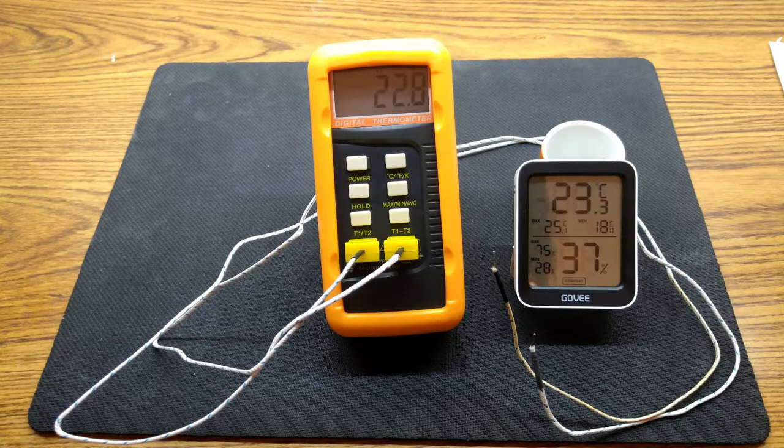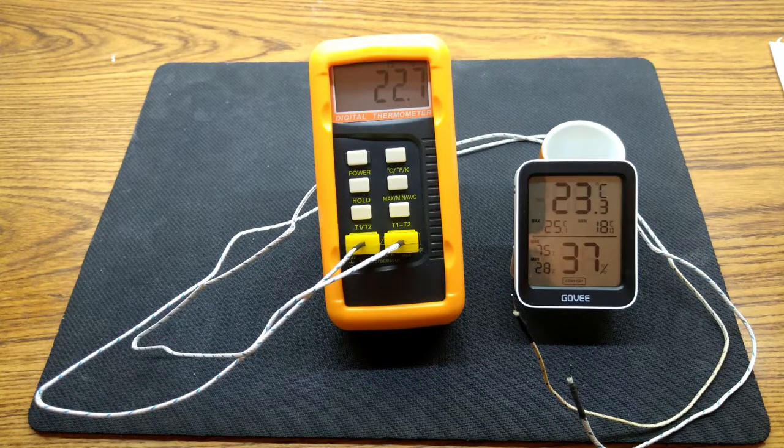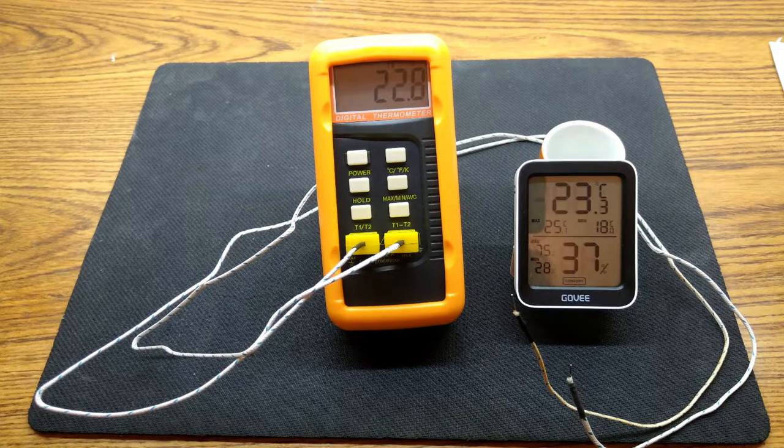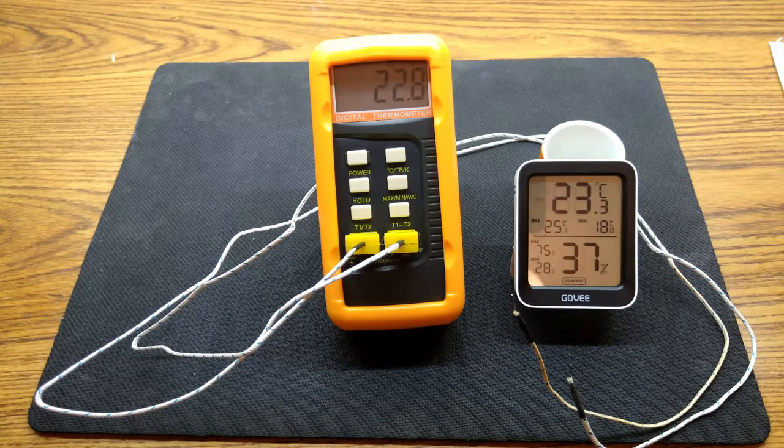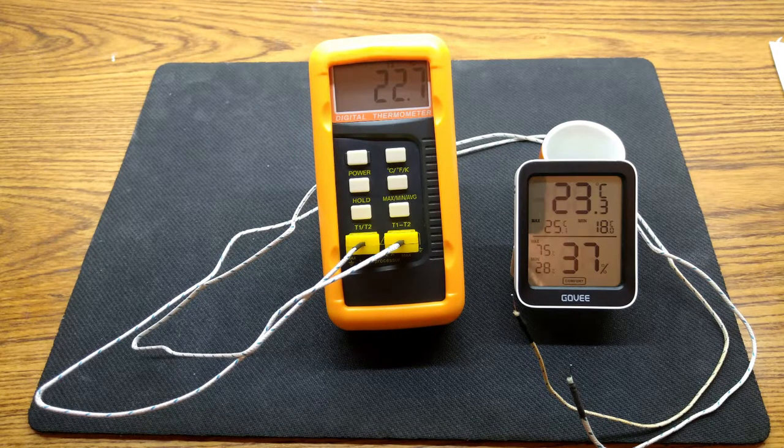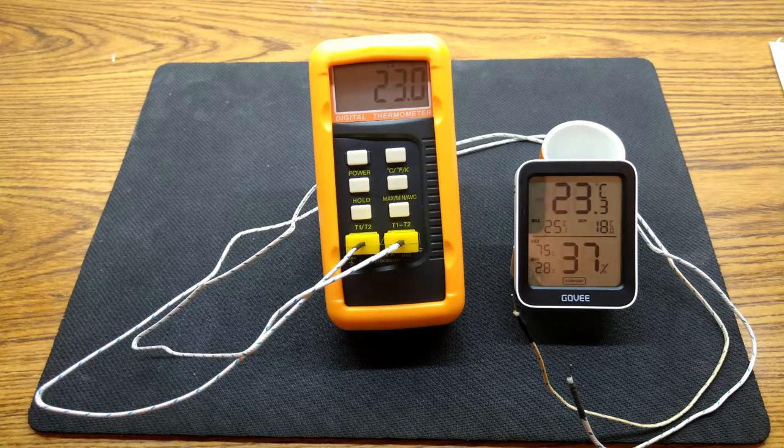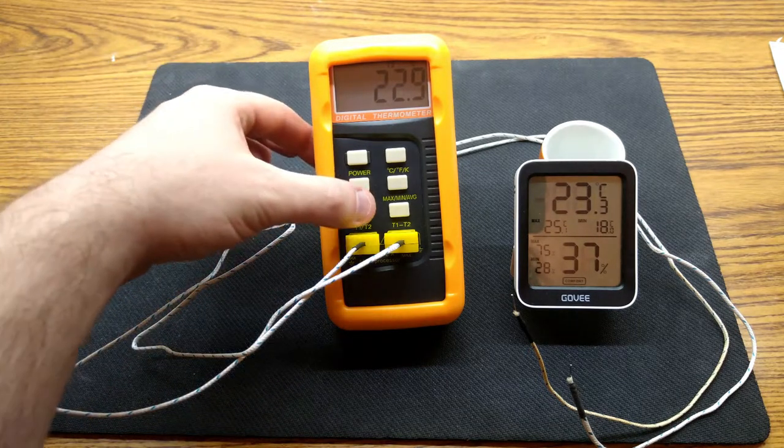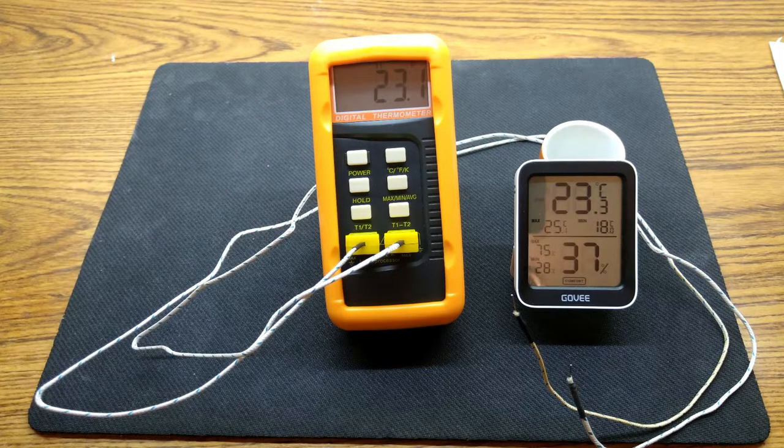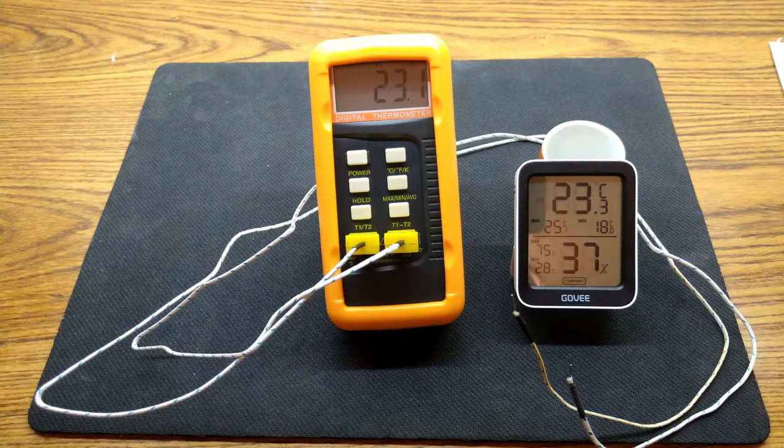Now it claims to have an accuracy of plus or minus 0.5 degrees Celsius, and for ambient temperature when compared against the Govee, this certainly appears to be the case. We can see that it's within 0.5 degrees Celsius of the ambient temperature.